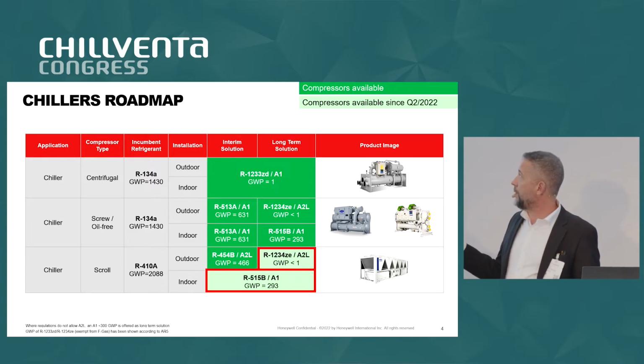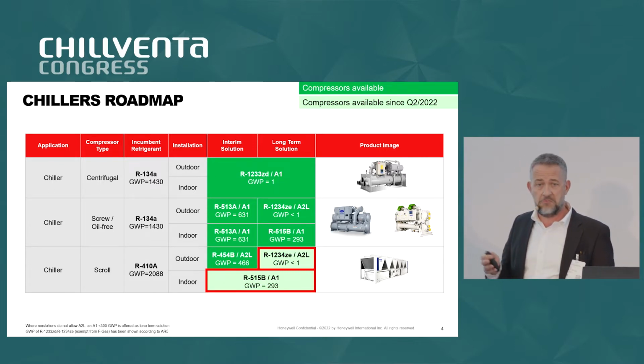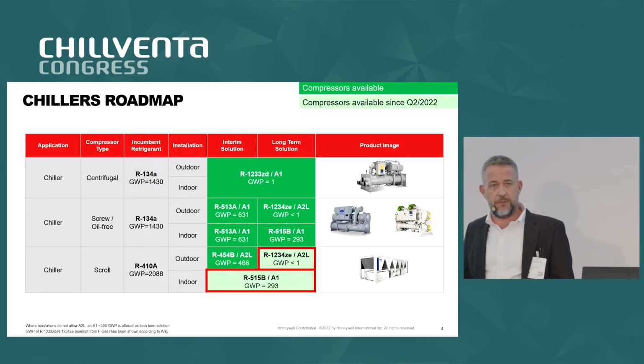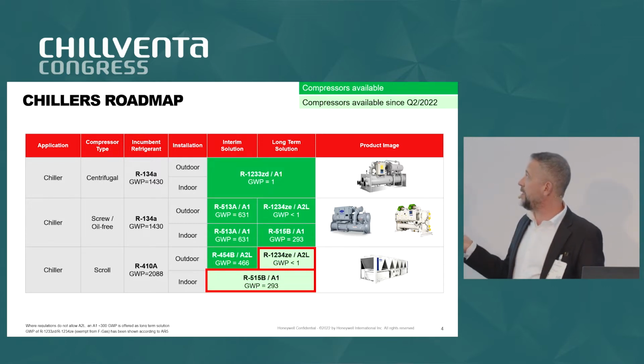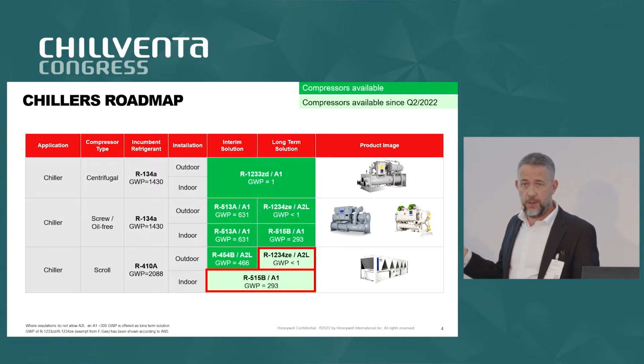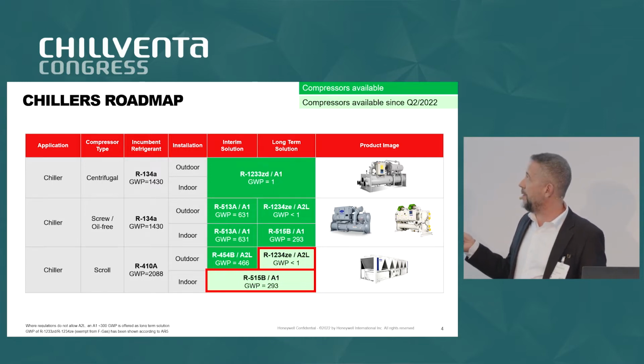But this is A1. So we have two options, whether this is for outdoor, indoor, or very special underground situations, very small machinery rooms, large charges. So there is today, as we speak, an option to stay A1 while going down to less than 300 GWP anyway. The beauty of it is that the highest performance we reach with ZE, we can access with 515B.